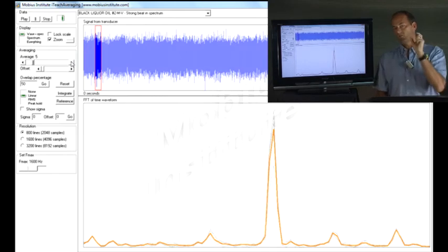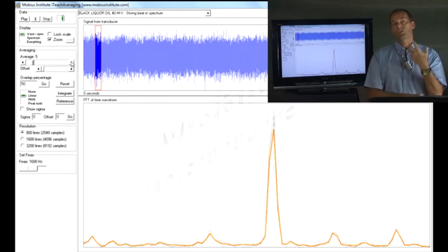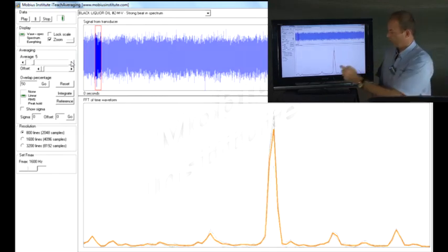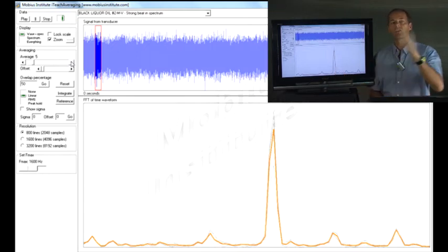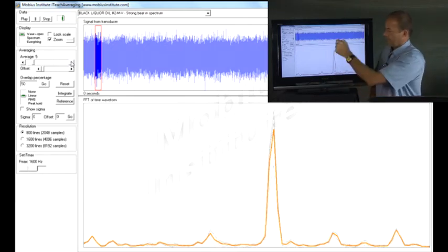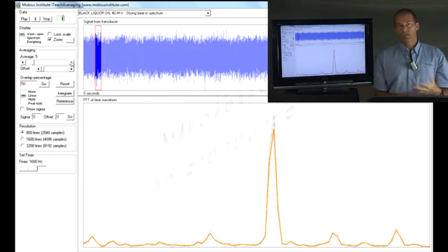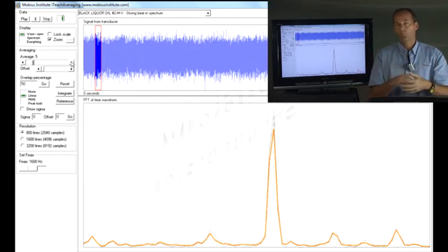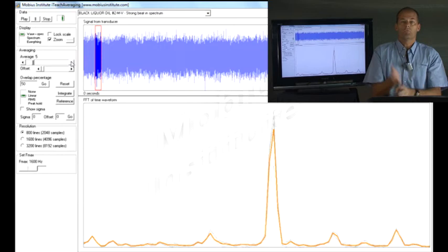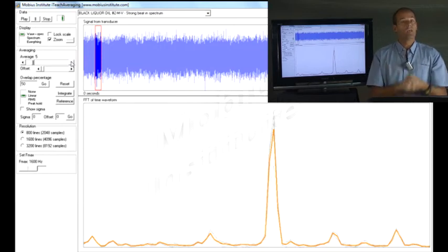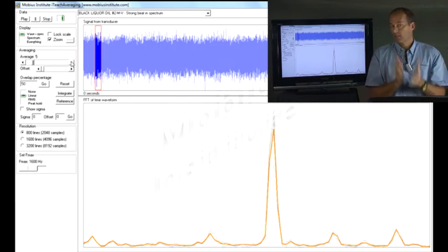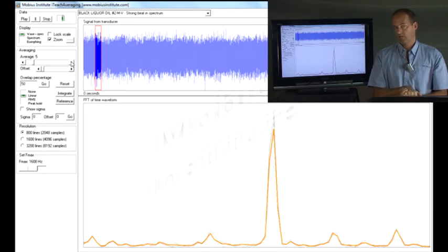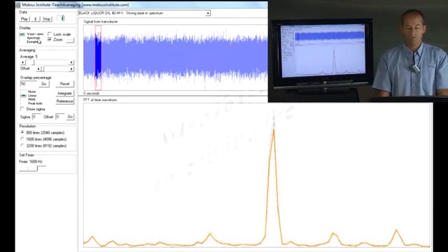So you see that having a short number of averages can get you into trouble. If your first measurement had a little itty-bitty peak there, you'd take no notice. Second spectrum had a great big peak, you'd be thinking, where's that vibration come from? What has changed in the machine between last time and this time? Absolutely nothing has changed in the machine. You've just taken too few averages.